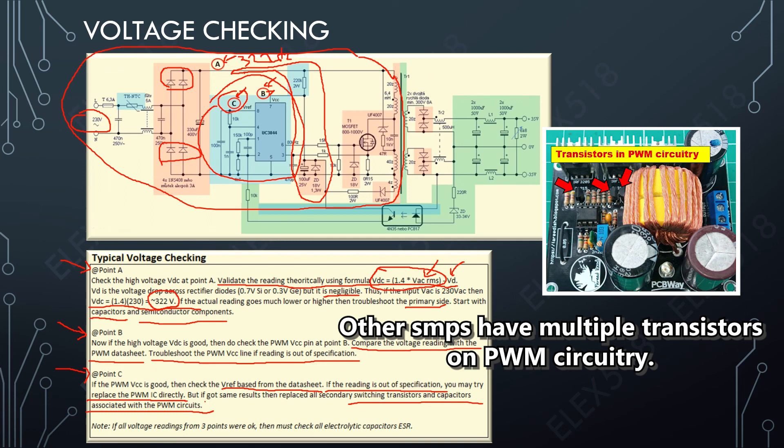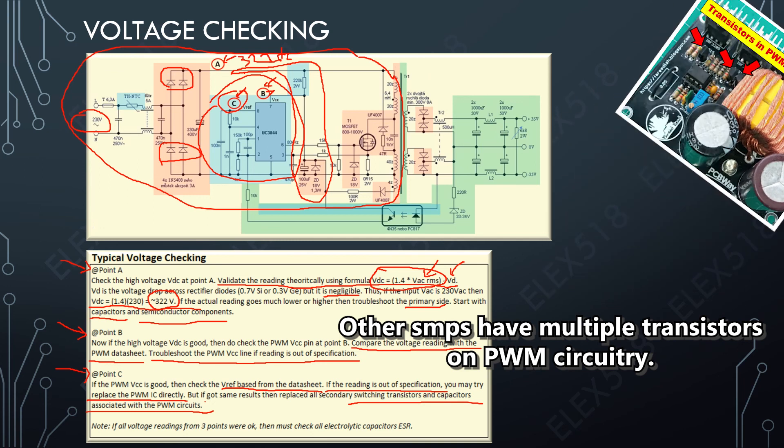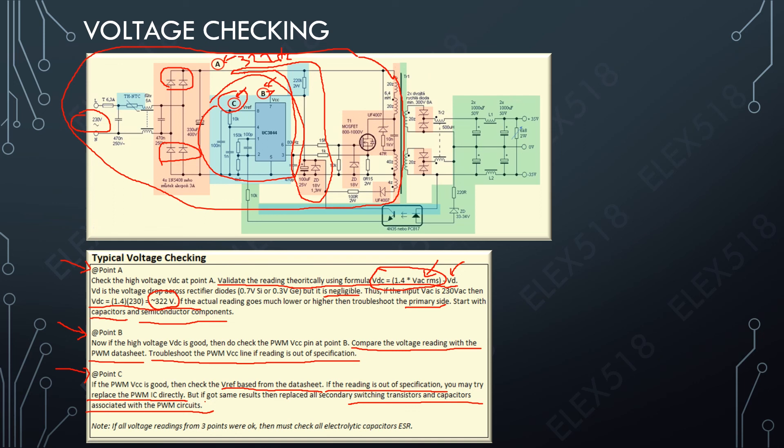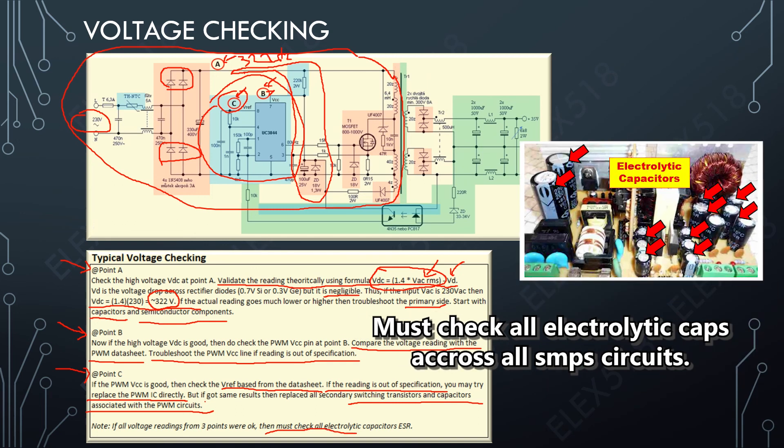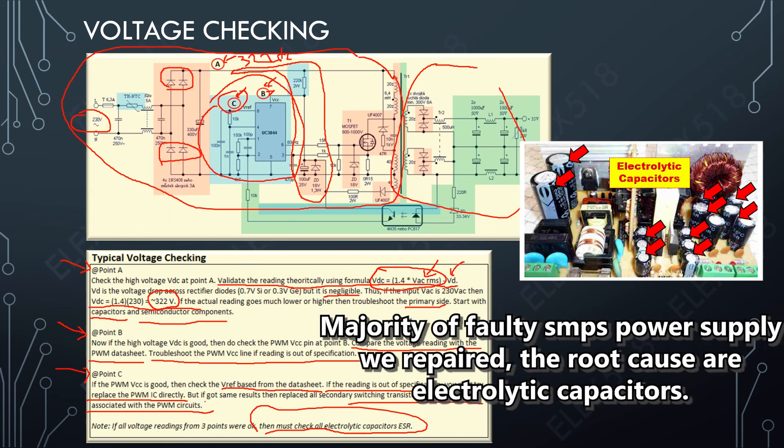Let's say all the voltage readings from three points were okay. What do I want to do next? I must check all the electrolytic capacitors from the circuit, including the primary and secondary side, because most of our experience shows that the power supply problem is caused by electrolytic capacitors.